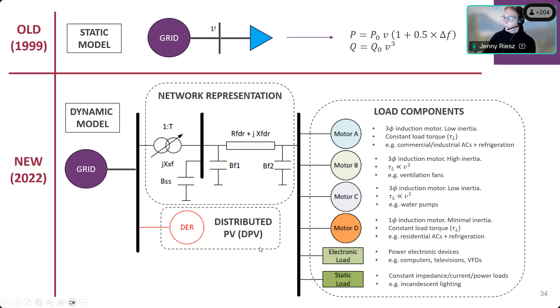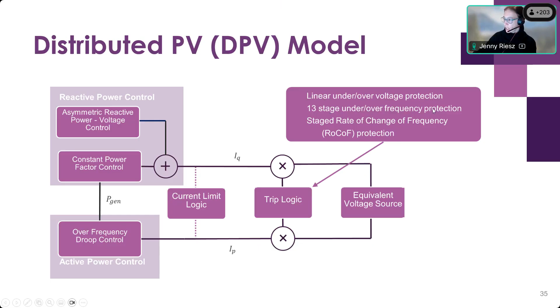We've absolutely been adopting the composite load model and distributed PV models from those efforts. The distributed PV model itself has many different elements: reactive power controls, active power controls such as over-frequency droop, which is an element of the Australian standards, and the tripping logic, including over and under voltage in a linear manner, multi-stage over and under frequency protection, and rate-of-change-of-frequency protection as well.